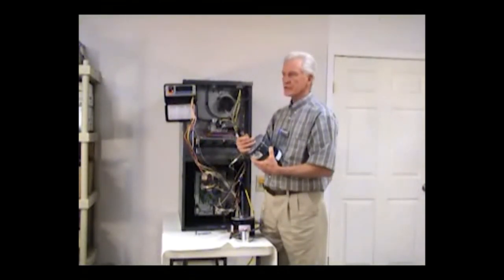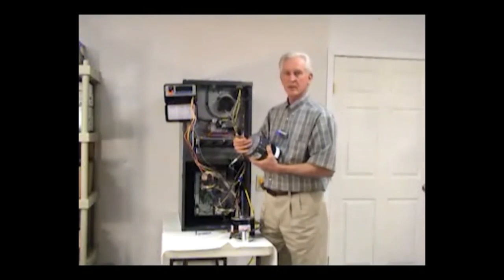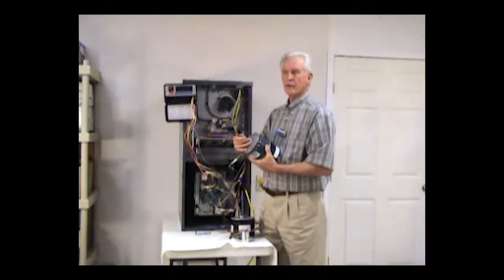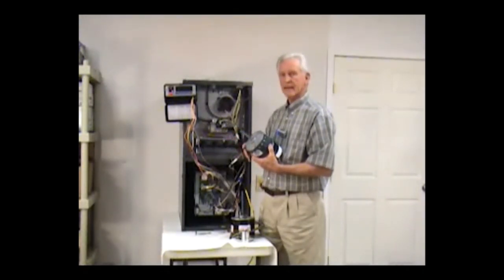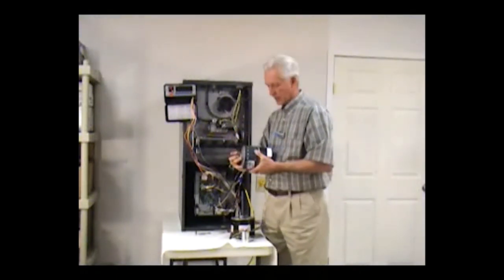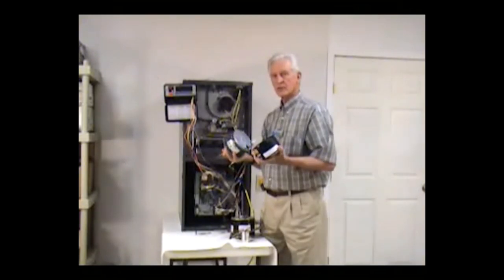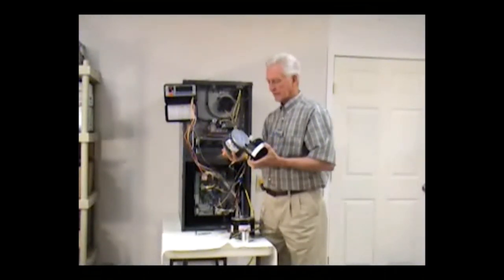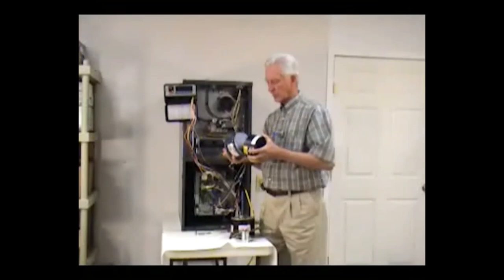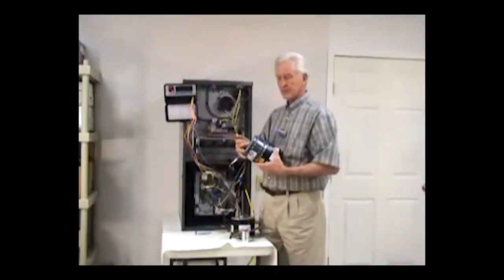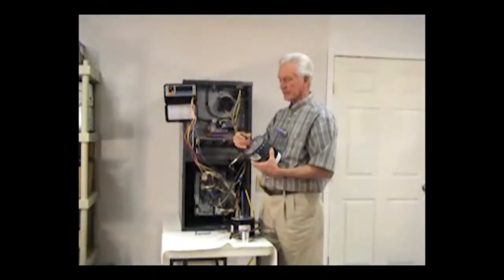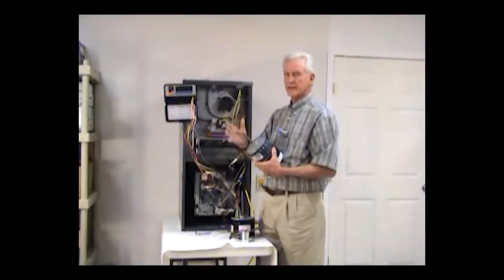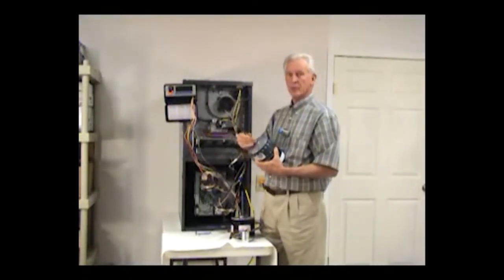And manufacturers have done lots of research on motors that have been returned where they are finding that as many as 40% or higher of motors are returned saying that we have bad bearings, bad motor, something in this part of it is bad, when all we needed to do was to change the module out, and that would have resolved the problem because the actual module had failed. So something that you might want to remember, that if you're looking at a motor and you're turning the shaft, that does not always mean that you actually have a problem with that.